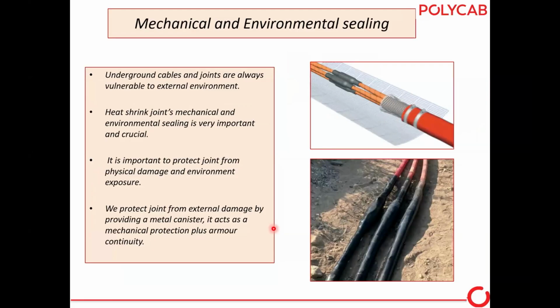Now for the fifth part, mechanical and environmental sealing. In the cables, we use the armoring. Armoring has two purposes. The first one is mechanical protection, and the second one is short circuit current. So we give the BB canister. That canister is there. Armoring is used for mechanical protection and also for the short circuit current.